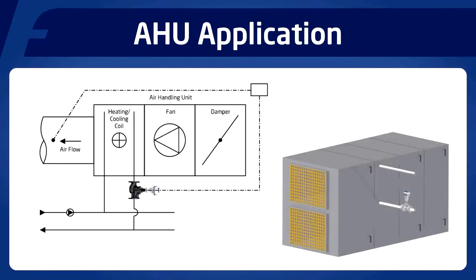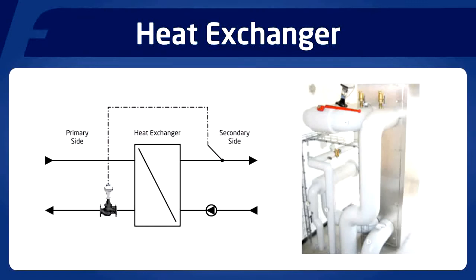There are two main applications for the flanged pressure independent control valve. Firstly, controlling the flow through an air handling unit. The second key application is mounted on the primary side of a plate heat exchanger, where the valve modulates open and closed under the control of the supply temperature on the secondary side of the plate heat exchanger.